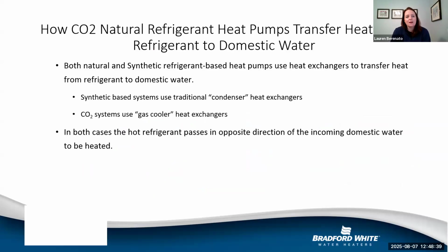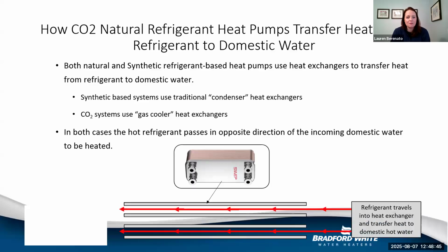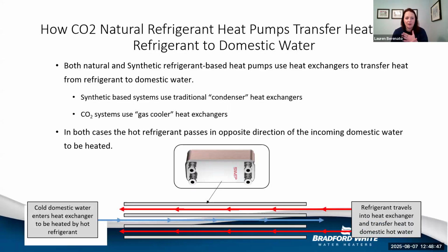Now, for CO2 natural refrigerant heat pump for refrigerant to domestic hot water, this is where we're seeing it's basically showing the differing ways that the refrigerant will travel into your heat exchanger and transfer heat to your domestic water. That's the biggest thing that we want: the transfer of heat based off of the movement of heat versus creation of heat. So you have your cold domestic water that enters your heat exchanger to be heated by hot refrigerant, and then your refrigerant will travel into the heat exchanger and transfer heat to domestic hot water.